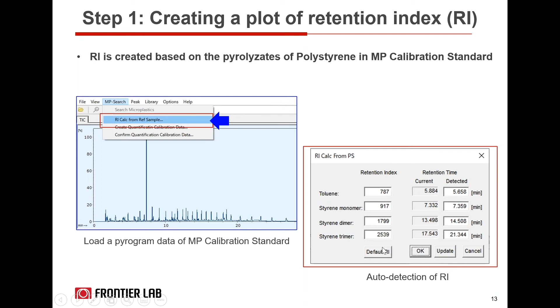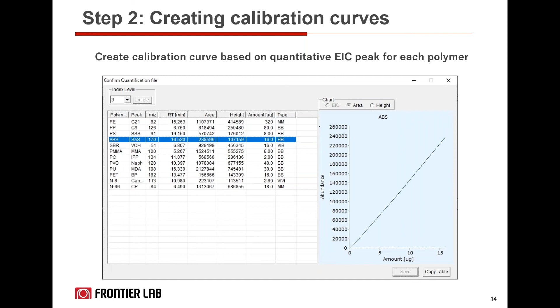The second step is creating calibration curves. In this case, your calibration curve is based on the quantitative EIC, the extracted ion chromatogram peak, for each of these polymers. The way F-Search MP 2.0 functions is that there is a characteristic peak, which we call the EIC, extracted ion chromatogram peak, for each of the polymers. That's how F-Search identifies and quantifies those polymers based on those EICs.